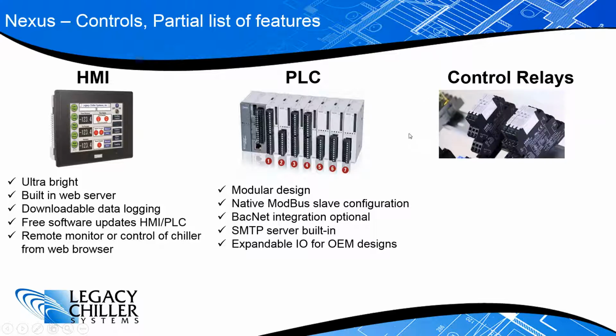We're going to zone in on this a little bit. Now, remember we talked about the printed circuit board and those relays. If you were to have a short, for example, on a compressor contactor or pump contactor, and it were to take out the relay on a printed circuit board, you'd have to replace the entire board.